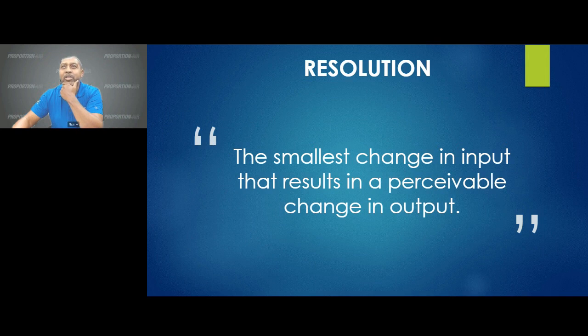Just the explanation of resolution is the smallest change in command that will result in a change in the output pressure. It can also be described as the ability of the transducer to resolve an output signal into units on a scale of the output device. High resolution means that a finer scale is used, which means the amplitude of the full scale is divided into smaller increments. This is critical when performing work like controlling microfluidic flows. When you have smaller increments to work against, it becomes easier to offer specific and even minute results or work at the cellular level. We achieve this high resolution pressure control through the use of a true proportional solenoid valve coupled to a unique analog PID control circuit. The true proportional valve eliminates digital stepping.